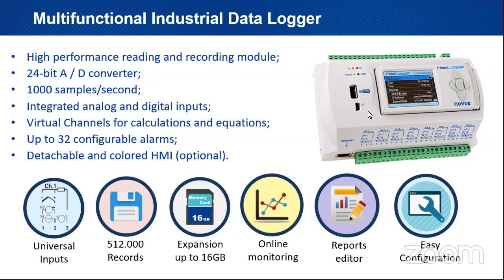So we're starting from the basics, from letting you know everything that the field logger has. Well, it does have universal inputs. What does universal inputs mean? Well, it accepts all temperature sensors, or most temperature sensors, PT100, thermocouples of several different types.